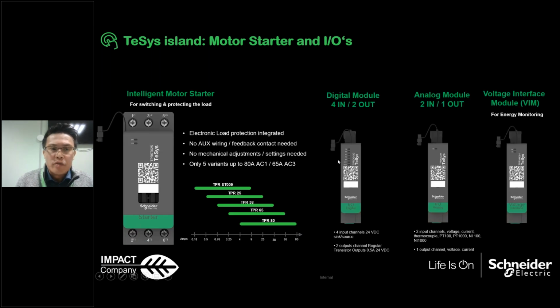In terms of the starters of the module, it's very simple: we only have five different references for the different applications. If you're familiar with the LC1D reference from Schneider, we have LC1D 09, LC1D 25, LC1D 38. They are the same. Now the 9 means 9A, 25A, 38A, and up to 80A. So everything for the motors below 37 kilowatts can be used in this island as a control.